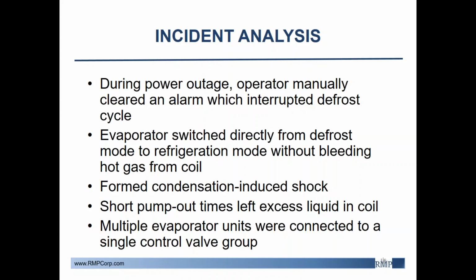So it's often recommended to put your evaporators on different valve manifolds so that you have less ammonia. For example, this was caused by a hydraulic shock incident, which means there was a lot of ammonia going through these, and since there were all these evaporators, one of them blew up and caused all of this ammonia to shock the system. If there'd been less evaporators on the one valve, perhaps it wouldn't have been as serious of an issue. Maybe it wouldn't have ruptured. Perhaps if it did, it would have been a less severe leak.